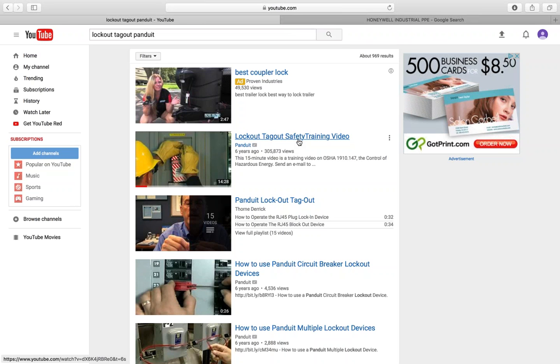So the energy isolation device is the engineered mechanism that's already in place for us to be able to turn the power on and off, right? Breakers, disconnects, items like that, pullouts. And then the lockout tagout device is what we use in order to lock the energy isolation device in an open position, so that we have no energy going to whatever pieces of equipment, tools, or processing units that we're working on, okay?